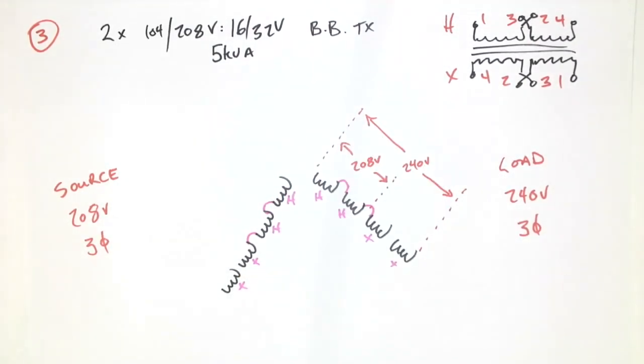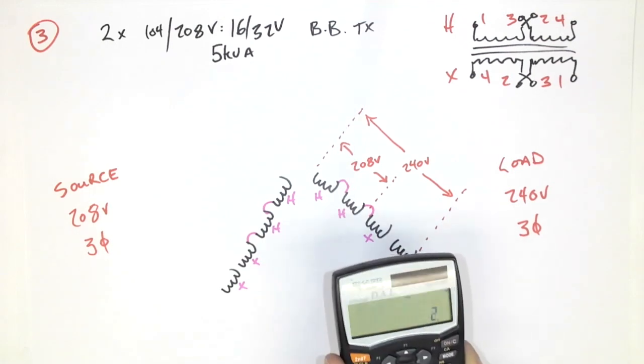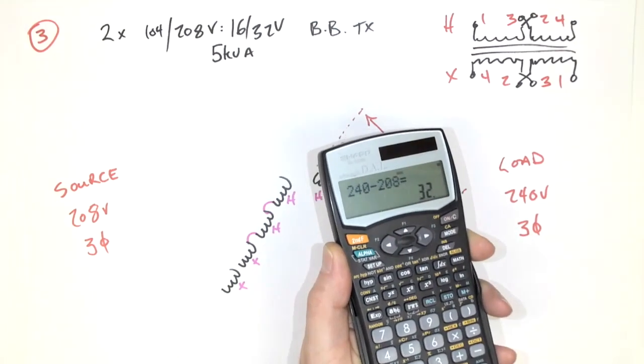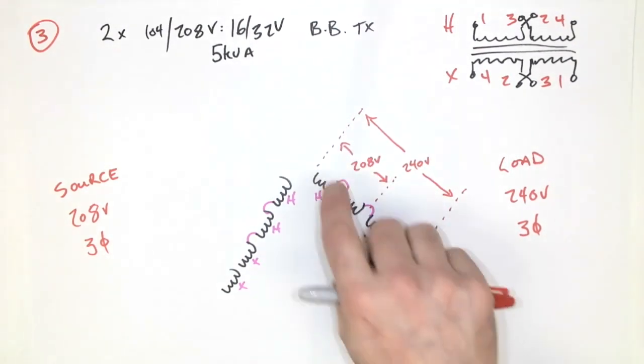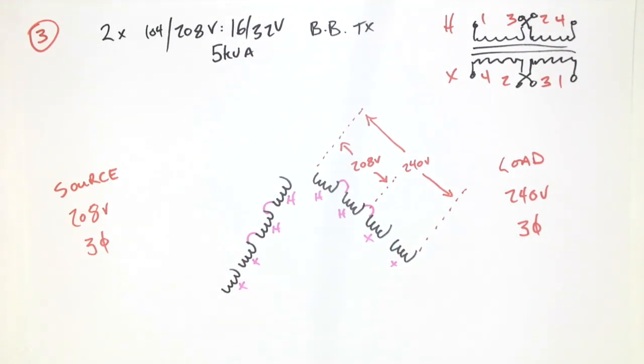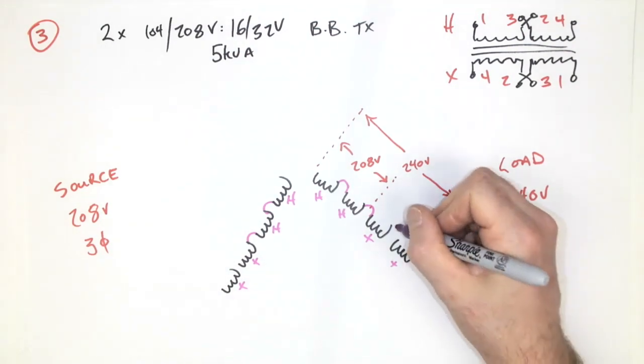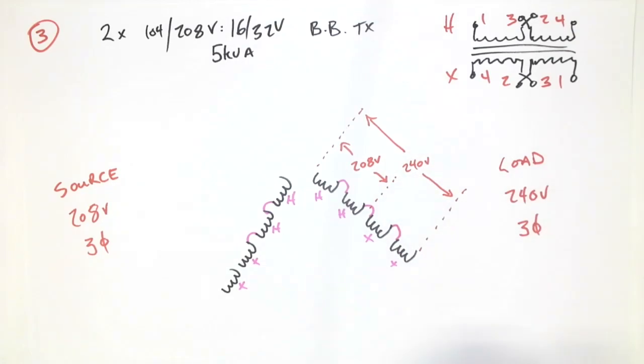All right, the next one is 1632. So I need to have 240 volts, and we can do a quick arithmetic here and just subtract 240 minus 208, which gives me 32 volts. So that tells me that here, those two windings must be connected also in series. Now that we've determined this, we can complete the remainder of the connections.